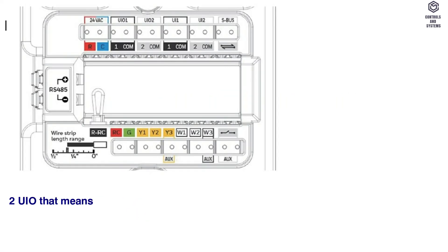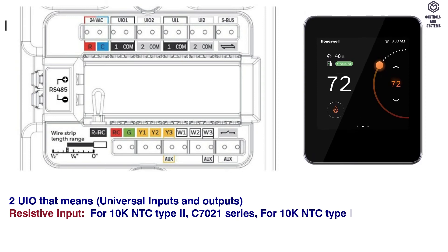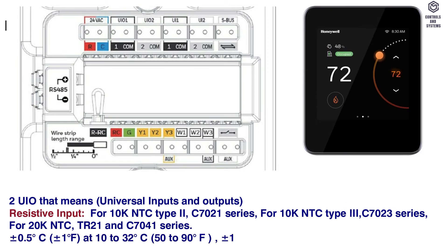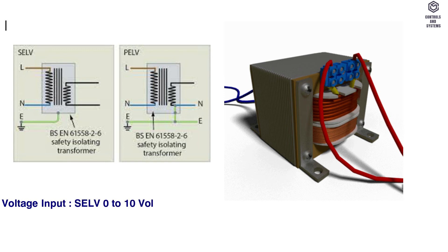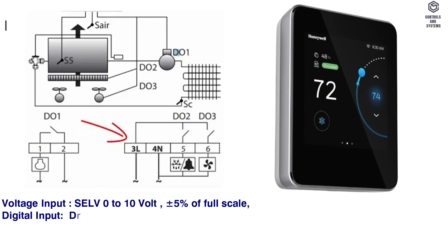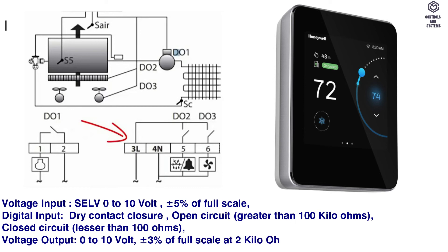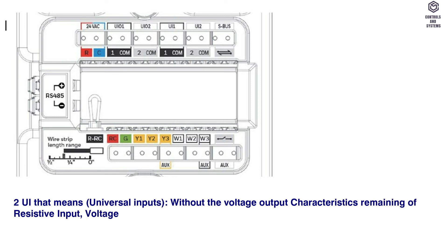I/O characteristics — Universal Inputs and Outputs (UIO): Resistive input supports 10K NTC Type 2 (C70-21 series), 10K NTC Type 3 (C70-23 series), and 20K NTC (TR-21 and C70-41 series). Voltage input: SELV 0 to 10V, ±5% of full scale. Digital input: dry contact closure; open circuit greater than 100K ohms, closed circuit less than 100 ohms. Voltage output: 0 to 10V, ±3% of full scale at 2K ohms. Universal Inputs (UI) share the same resistive input, voltage input, and digital input characteristics as UIO, but without voltage output.